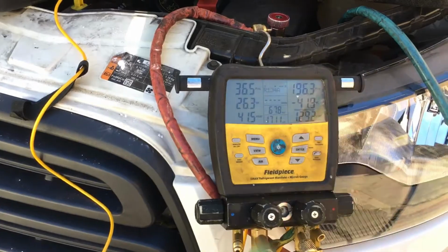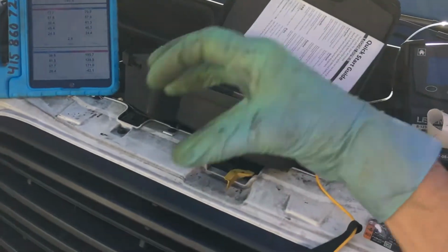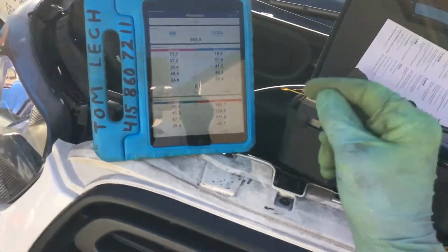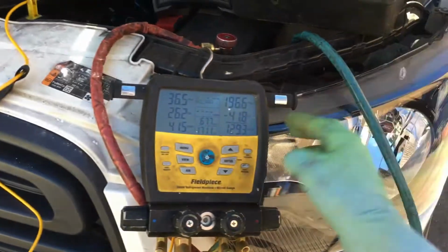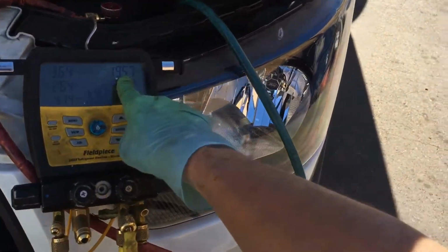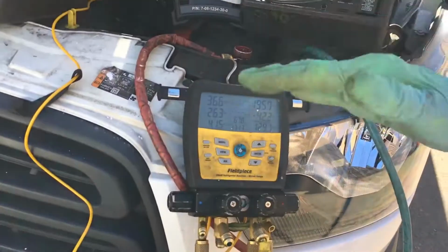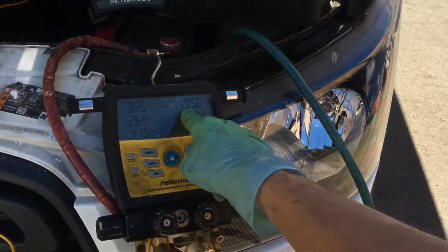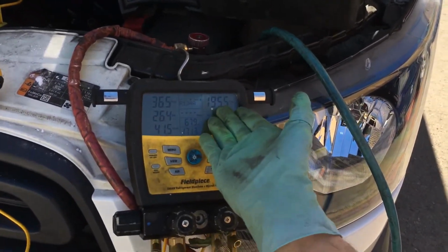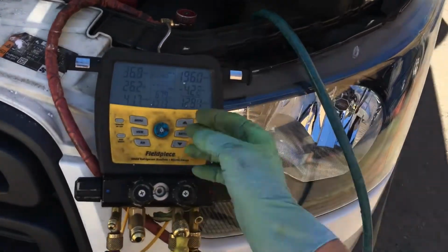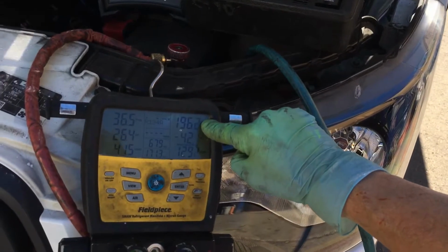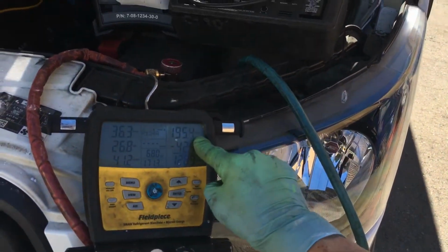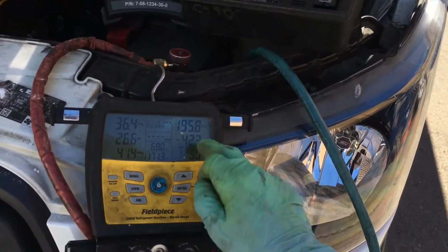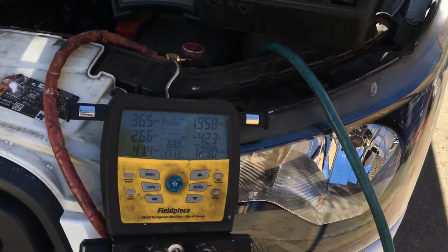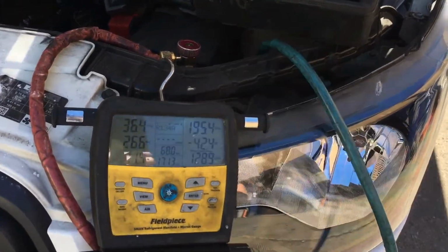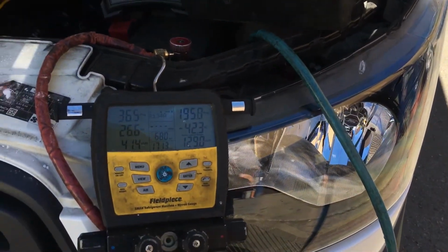If you were on a split system in a home, and you had 115 degrees going over your evaporator, you'd have to go back to the R12 days to get such a low head pressure at 115 degrees over the evaporator. But let's just pretend it's R410, and let's say it'd be 510 psi, 400 psi. But say you're on a residential split system and you had 115 degrees over your evaporator and you had 195 psi. Then you lowered the load on your evaporator down to 72 degrees and you still had 195 psi. What's going on?